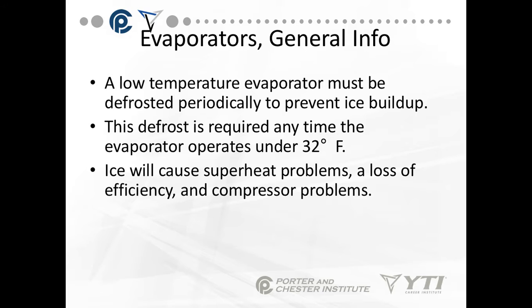So if the box temperature is maintained at 36 degrees but the evaporator is running under 32 degrees, you still need defrost. Ice causes superheat problems because ice is a great insulator — it actually prevents heat exchange from the air blowing across the evaporator. Ice will cause superheat problems and loss of efficiency, and eventually compressor problems because liquid refrigerant will start going back to the compressor.